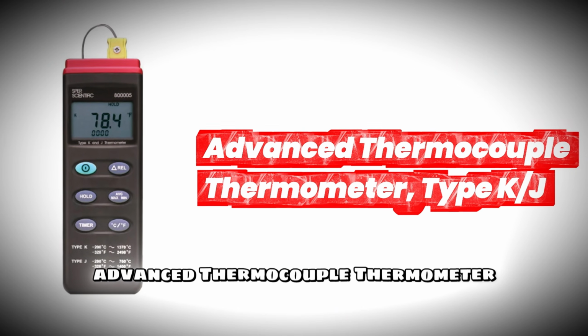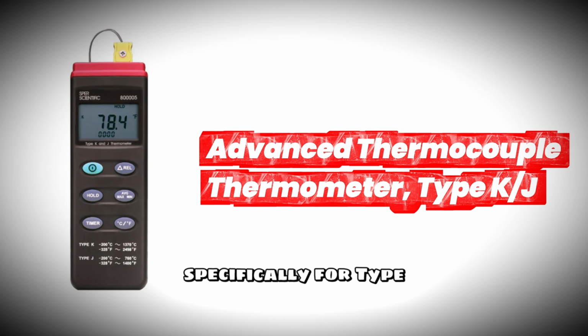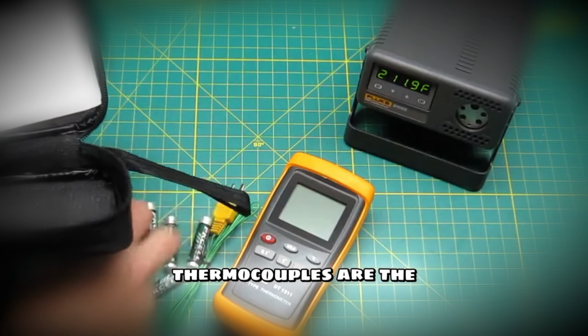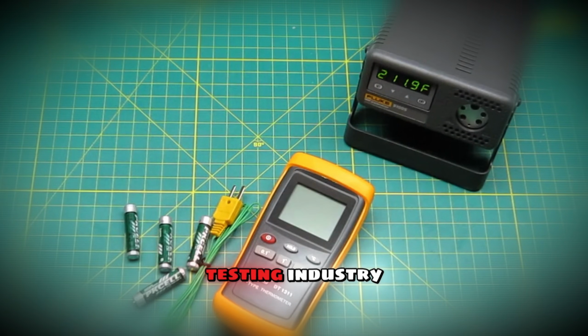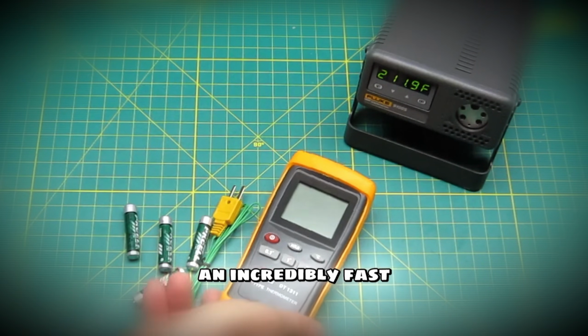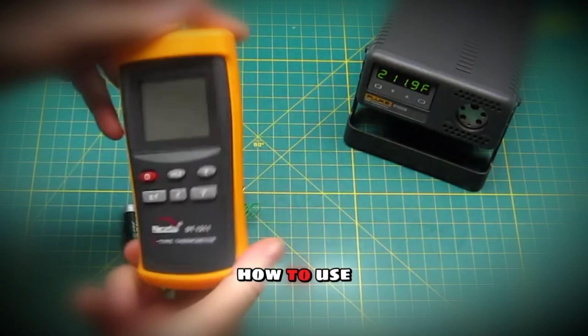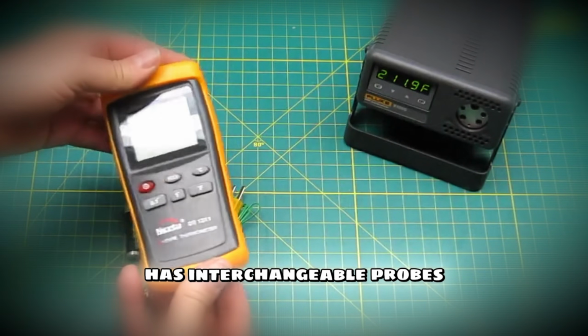Next is the advanced thermocouple thermometer, specifically for Type K and Type J probes. Thermocouples are the workhorses of the materials testing industry. They are rugged, they handle extreme temperature ranges, and they have an incredibly fast response time. How to use it? This unit has interchangeable probes.